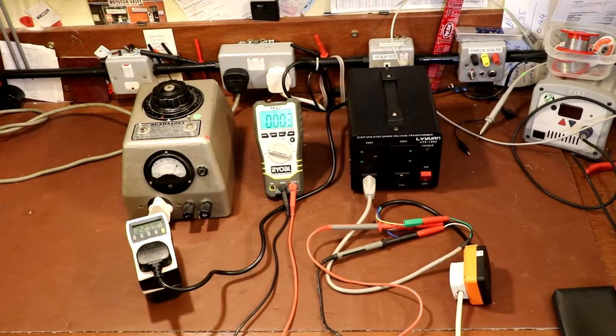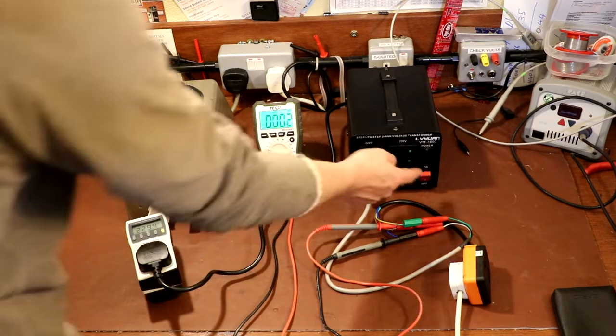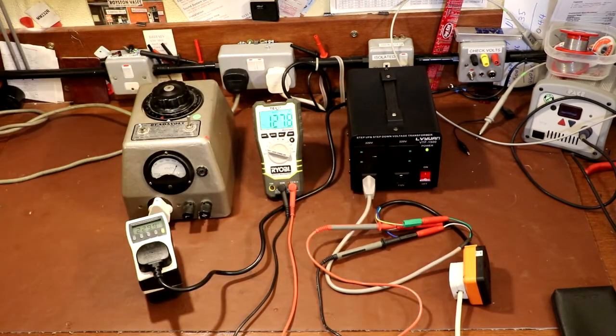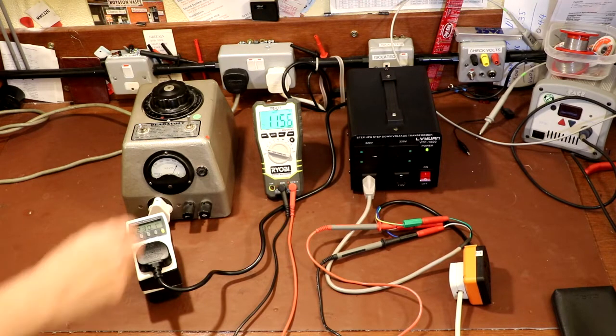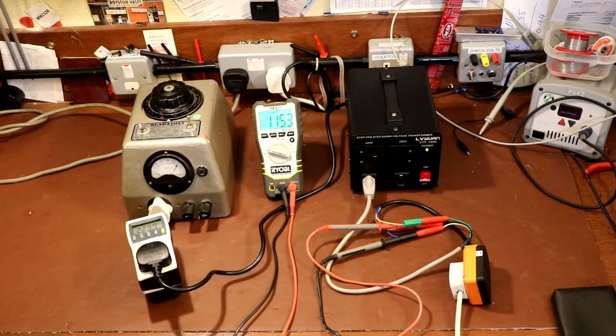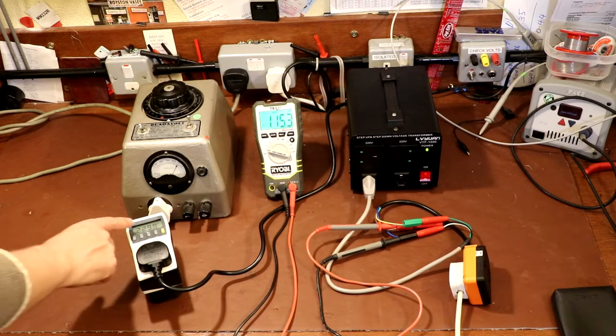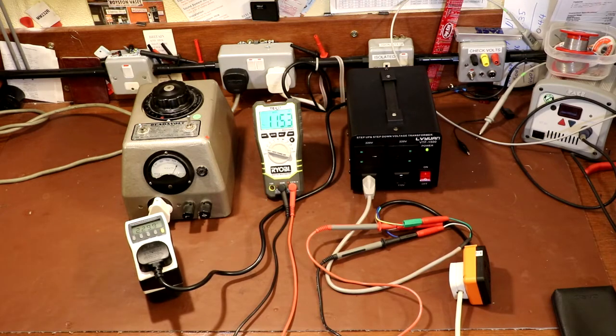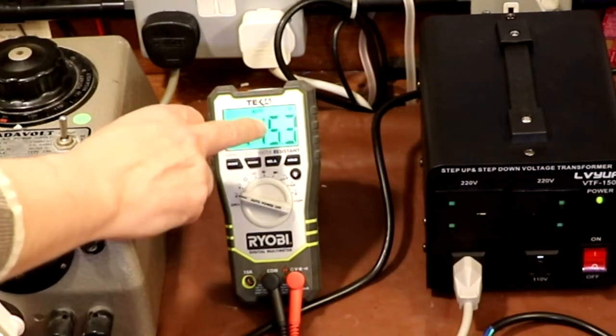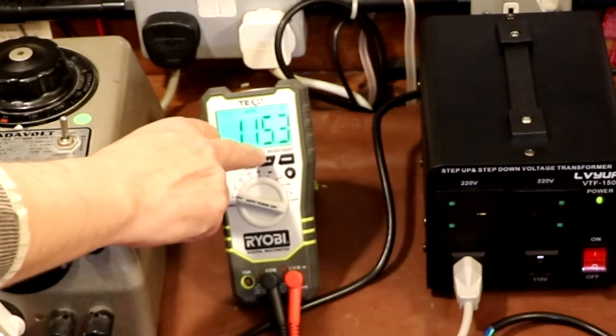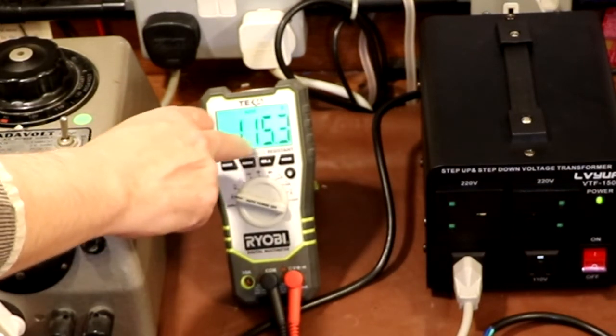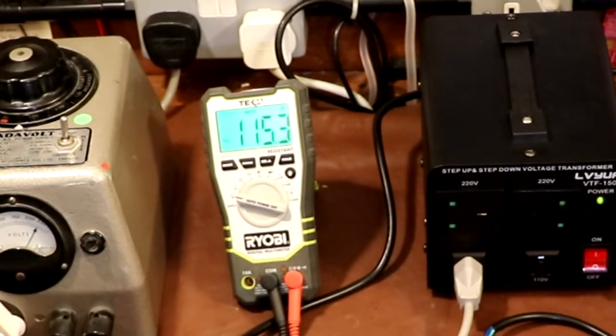So at the moment I've got the radiator under my bench switched off, so we're not going to be putting any load on the transformer. So we'll just switch the transformer on. And we're getting 115.4 volts out, and we're putting into it 230 volts. So what we need to do is we need to write down this, because this number is important for the test. So we need to write down 115.3 volts. So I'll do that.